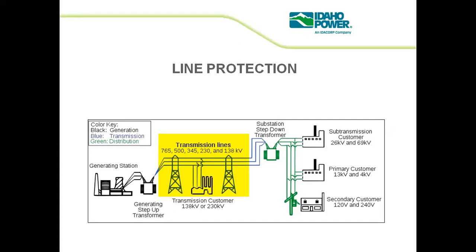But in most cases in India, we are basically using the overhead transmission line. When you use an overhead transmission line, the main equipment responsible to transfer the power from generating to grid to substation is basically the conductor. The conductor we can use is the ACSR conductor, having different configurations depending upon the voltage level, the power level, and the current handling capacity you need to transfer from generating to the grid. So depending upon the voltage, power, and current, we rightly choose the conductor. These conductors are available at different ratings, and all of them are basically ACSR conductors, whose full form is aluminium conductor steel reinforced.